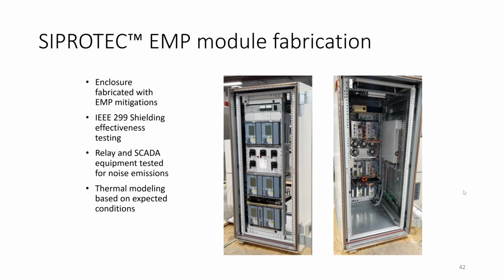In testing, what we were able to do was first the IEEE 299 test, which allowed us to check for shielding effectiveness. And then we also subsequently performed a system level test with an unclassified E1 pulse. Both of those confirmed that we were achieving over 100 dB of attenuation. And then we also went to the step of doing direct injection testing up to 80 kV, and using the surge suppression did allow us to protect those devices.